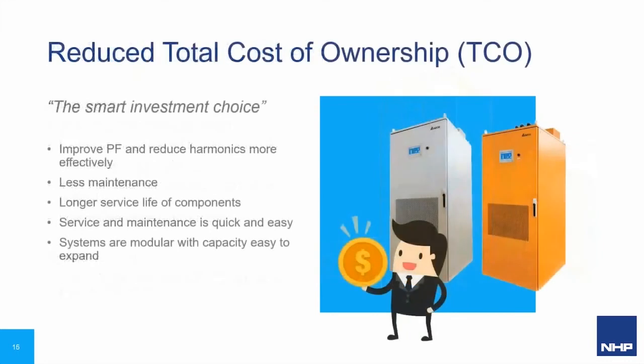So while up front the price of an SVG or an APF is higher than traditional methods of power factor correction, it does have reduced total cost of ownership. Not only does it improve power factor and reduce harmonics more effectively than traditional methods, it has less maintenance and longer service life of components. So your service and maintenance is quick and easy. You don't have to constantly check capacitor levels and replace them over the years. These systems are also modular, with easy expansion of their capacity for future expansion.